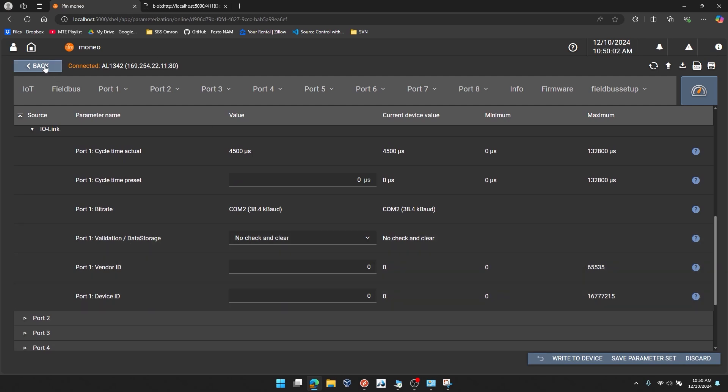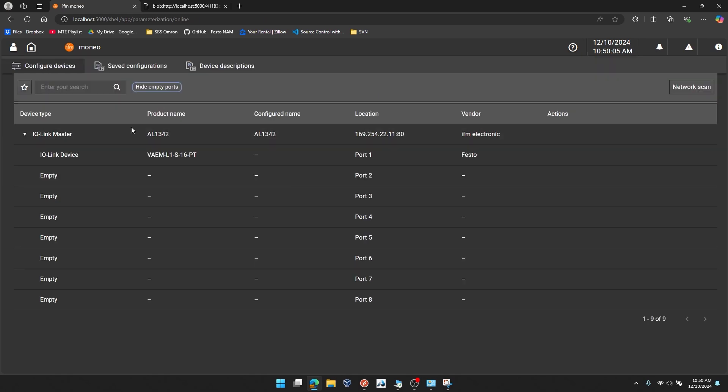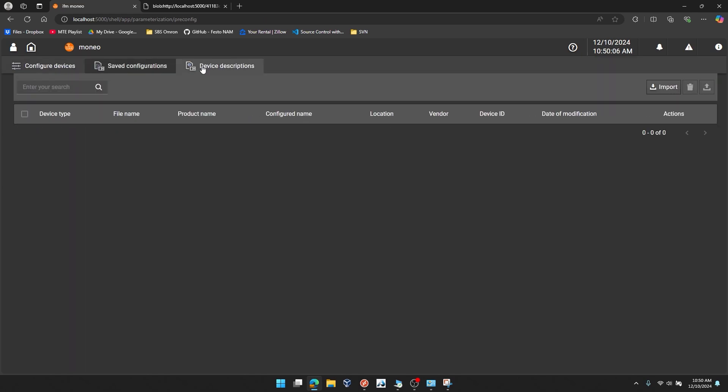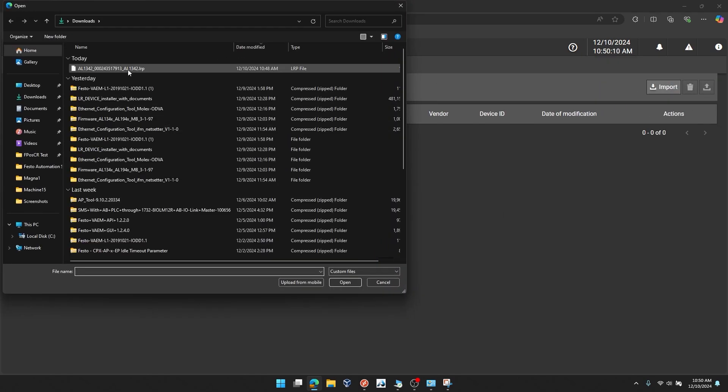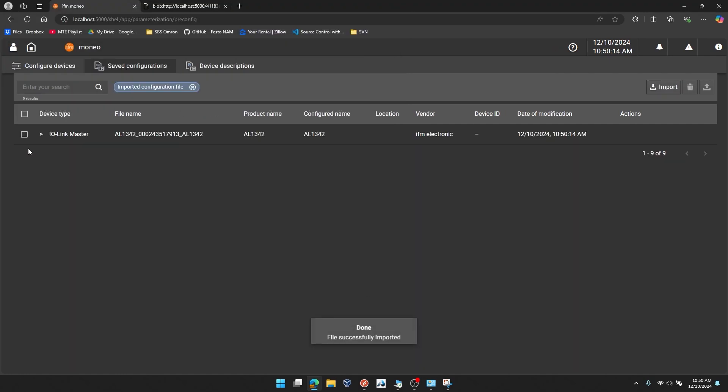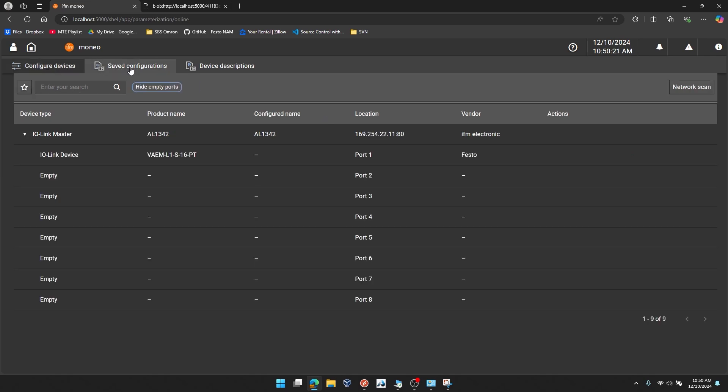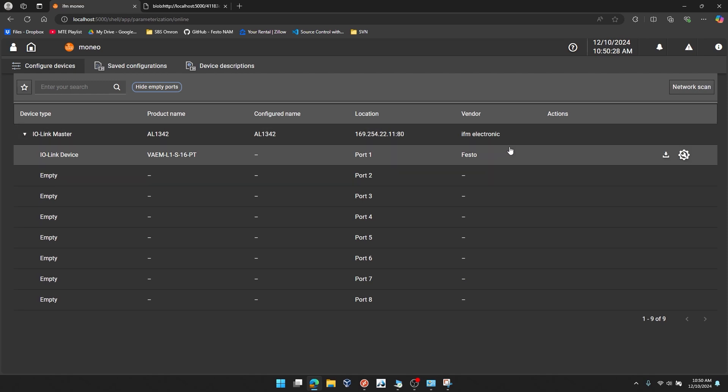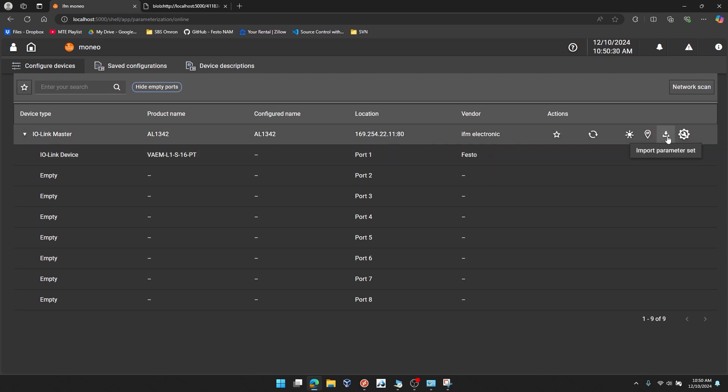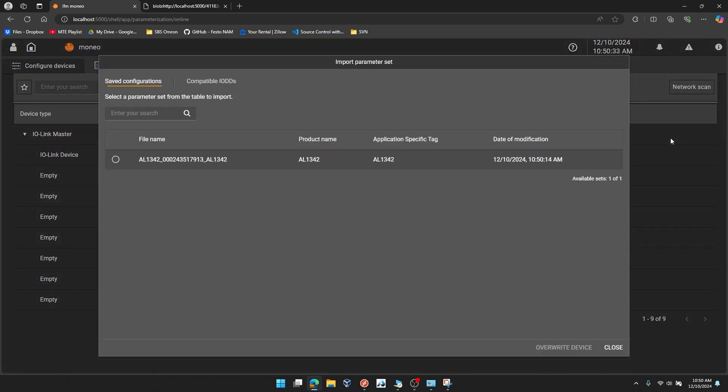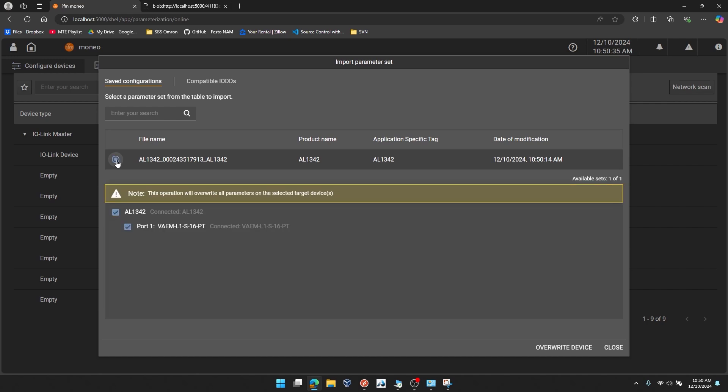So if I want to use that parameter set file to configure this IO-Link master, I am going to import the parameter set that I downloaded. I'll click open. That's now added that parameter set to Moneo, the software here. I'll go back to configure devices. And if I hover over the IO-Link master, not the individual ports or devices, I can go to the far right and you'll see import parameter set. It shows the one and only parameter set that I have in that saved configurations tab. I can check all the ports that I want to configure and I'll click overwrite device.